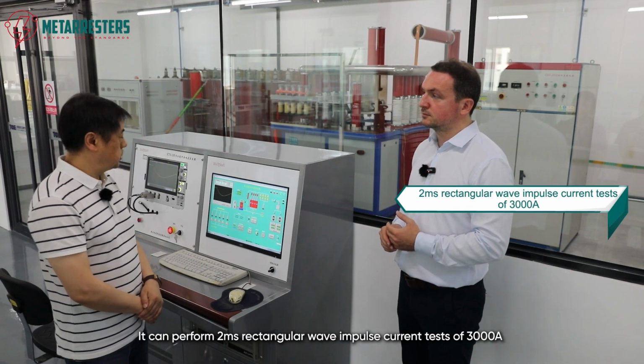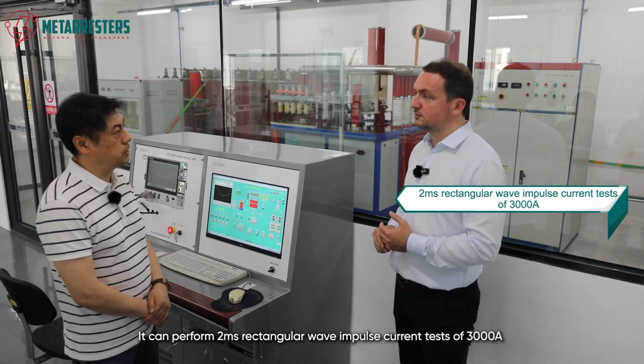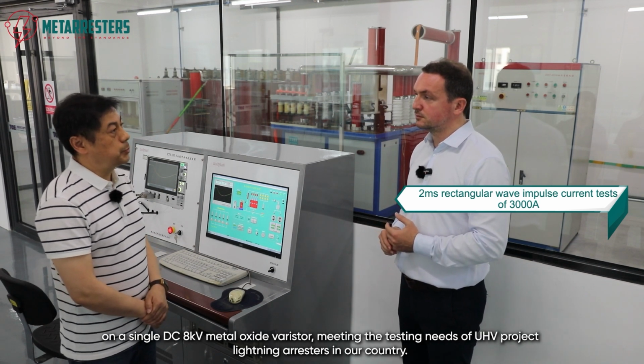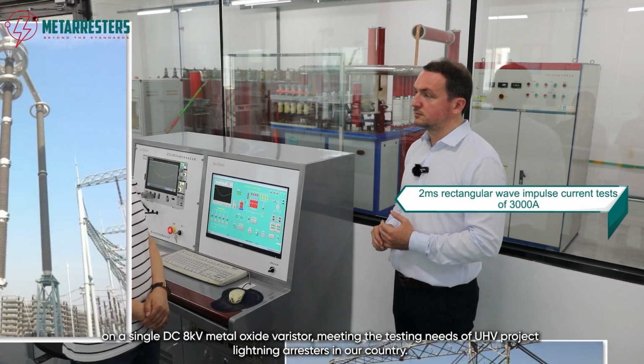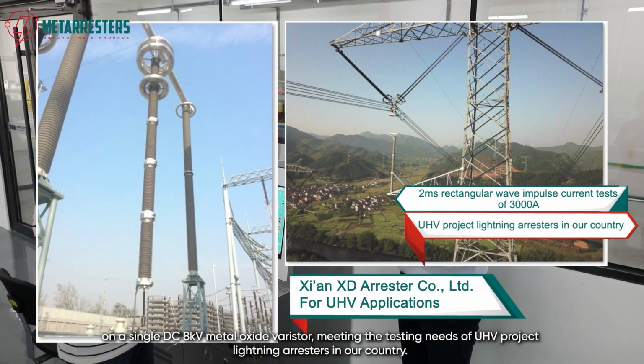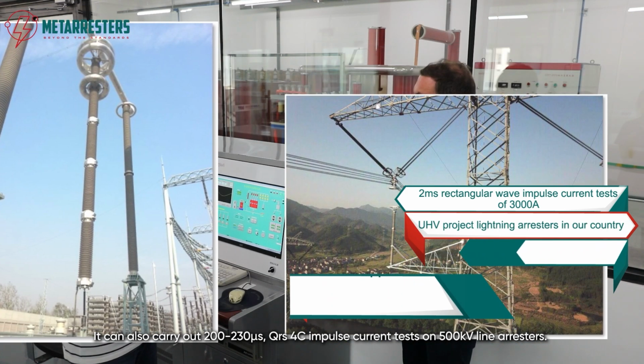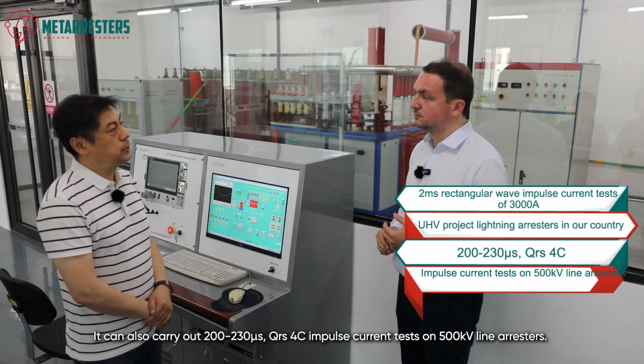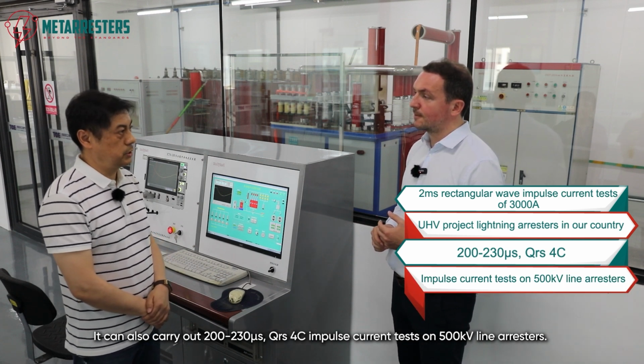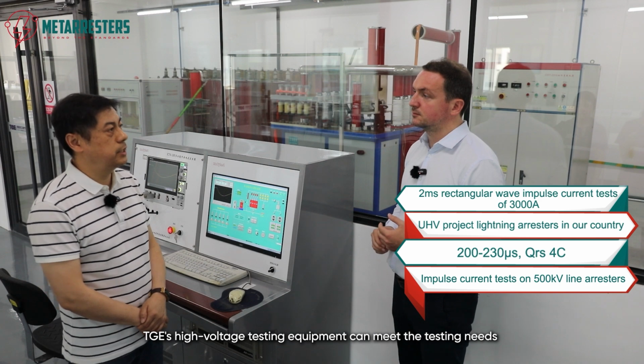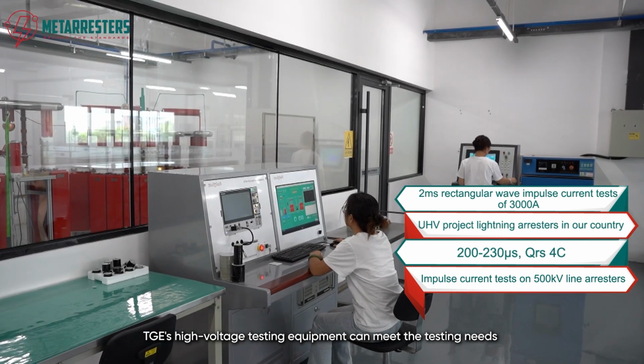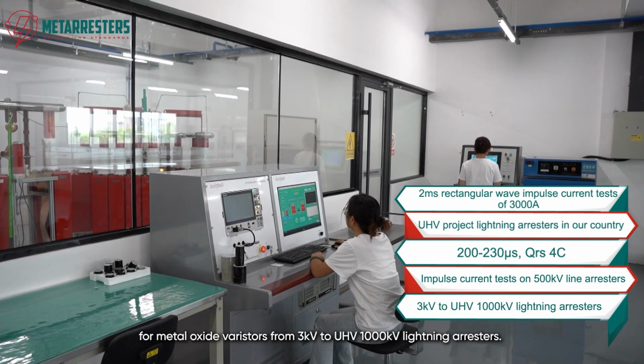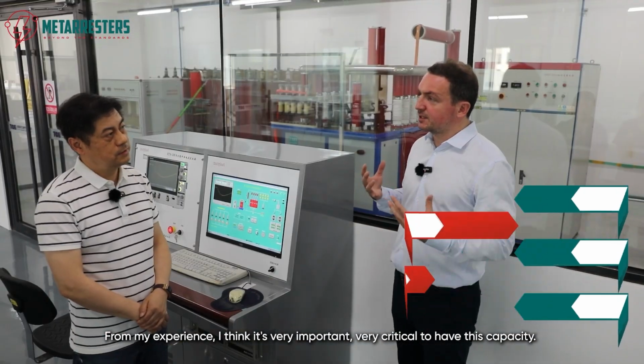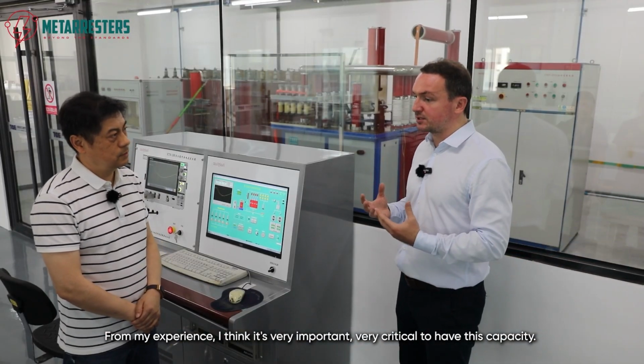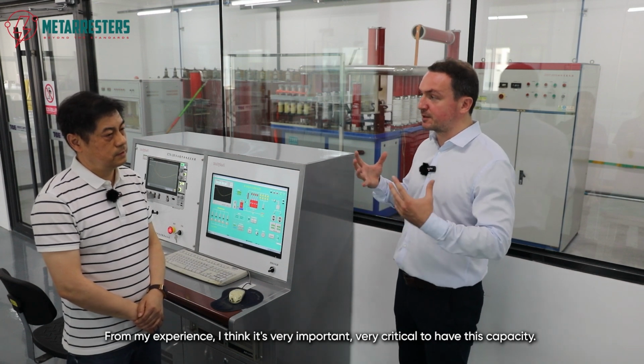It can perform 2 millisecond rectangular wave impulse current tests of 3,000 amperes on a single DC 8 kilovolt metal oxide varistor, meeting the testing needs of UHV project lightning arrestors in our country. It can also carry out 200 to 230 microseconds QRs 4C impulse current tests on 500 kilovolt line arrestors. TGE's high voltage testing equipment can meet the testing needs for metal oxide varistors from 3 kilovolts to UHV 1000 kilovolts lightning arrestors. From my experience, I think it's very important, very critical to have this capacity.